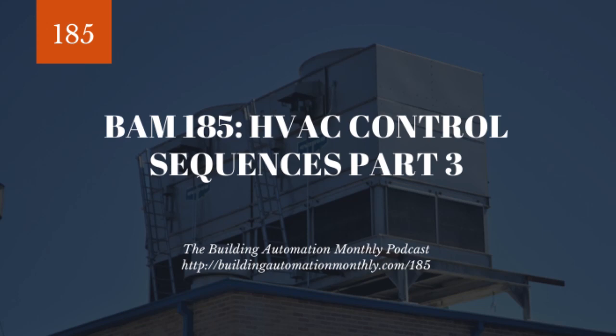And how that discharge air pressure is affected is when VAV boxes downstream from this VAV air handling unit close or open up, that causes the discharge air pressure of the duct to change. And what will happen is that the air handler will be monitoring the discharge air pressure and discharge air pressure set point and will vary the fan speed accordingly in order to basically provide the proper amount of air volume to these VAV units. Now, there's a couple little nuances here.